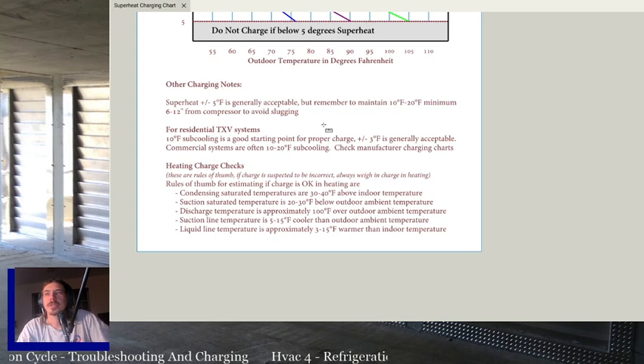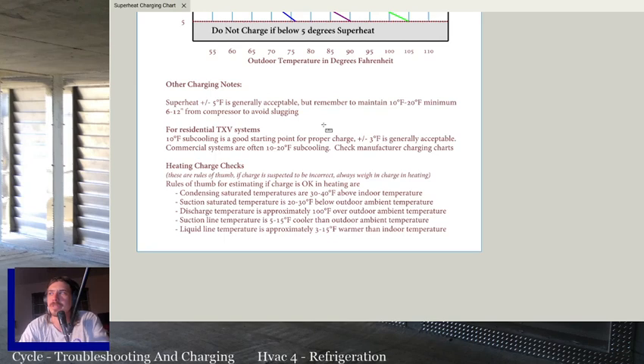So your discharge temperature, that's why you remember the absolute max on your discharge line's 180, right? Well, not your absolute max. The maximum recommended. Generally, you don't want your discharge line to be over 180. Something's going wrong. You don't want to run heat on a heat pump if it's 80 degrees outside, because your discharge temps are going to go high. But generally, they say, and I've never really tested this one that much, but it's a rule of thumb that's out there: 100 degrees over outdoor ambient should be about right on your discharge temp.